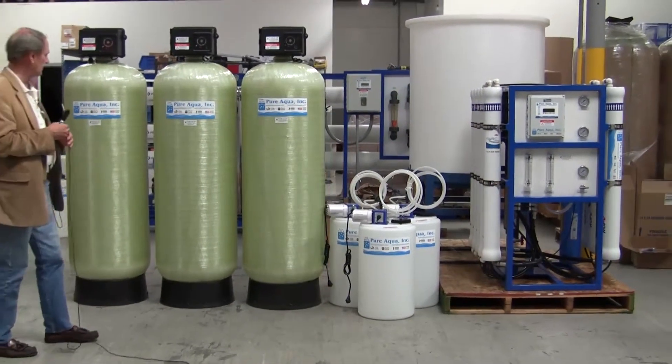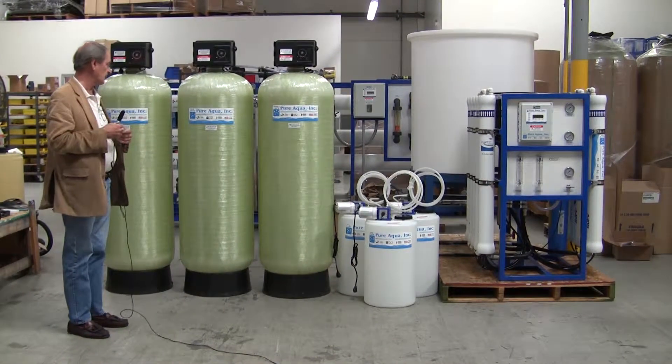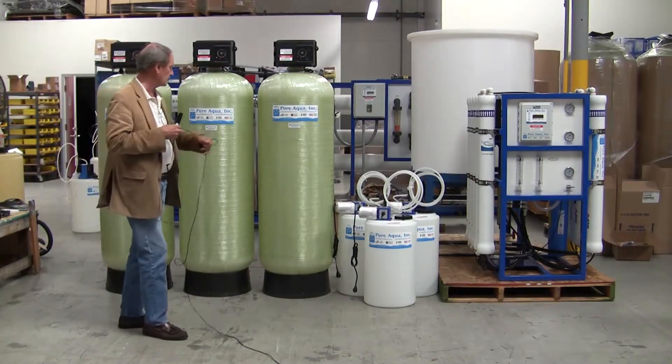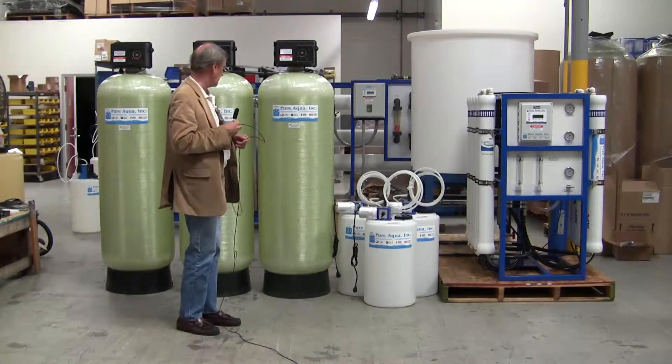Following the multimedia, we have a green sand filter which is primarily for the reduction of iron and manganese in the feed water, followed by activated carbon for the removal of organics and chlorine ahead of the reverse osmosis.